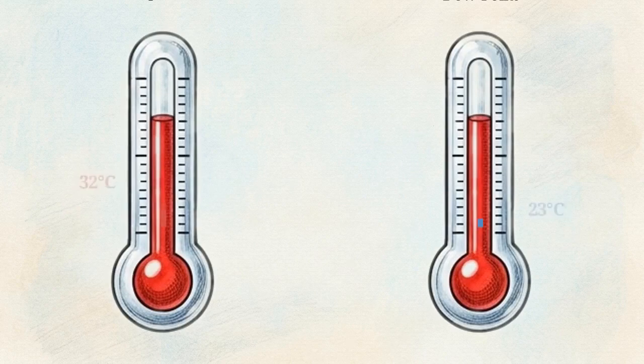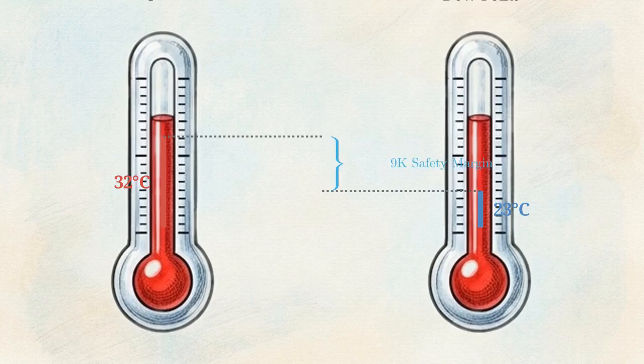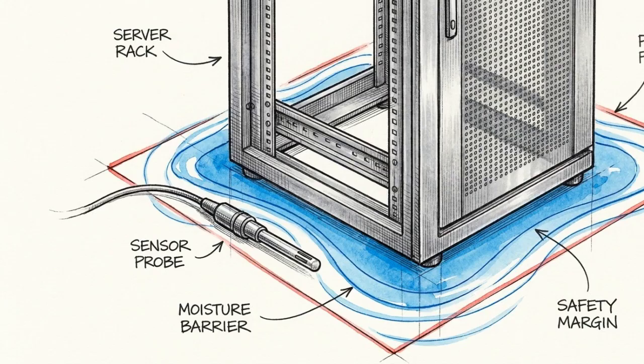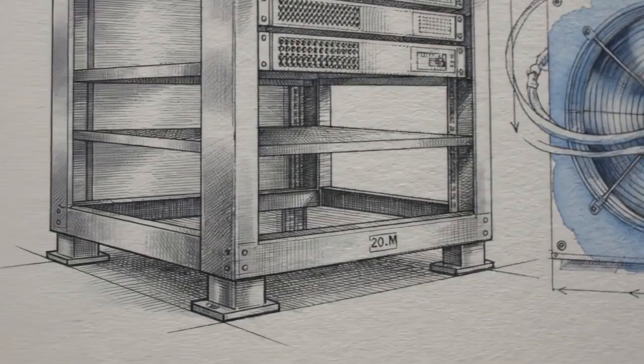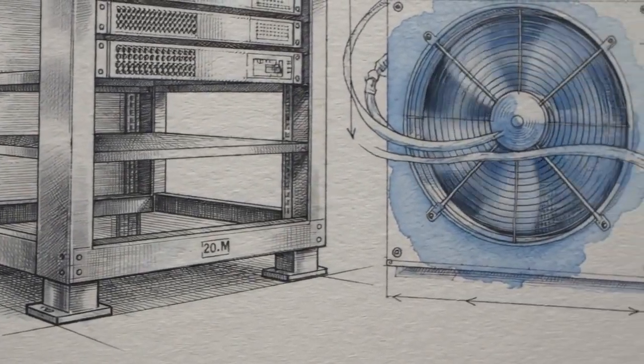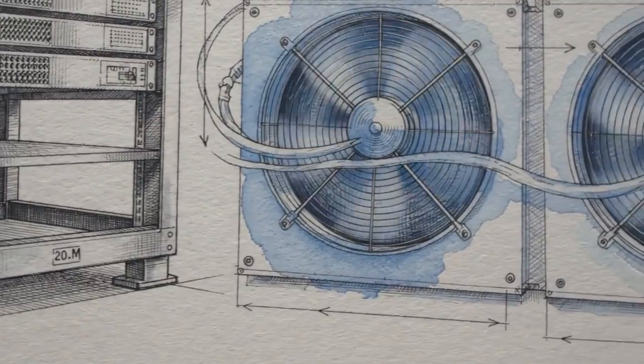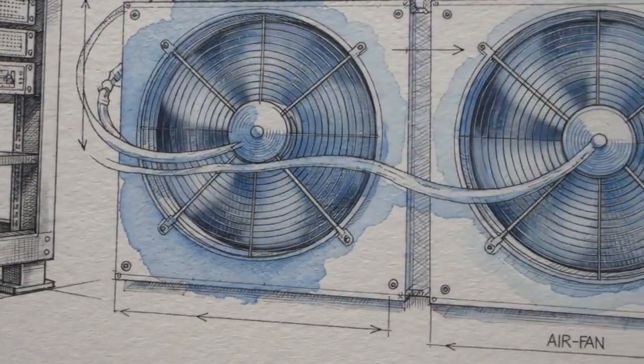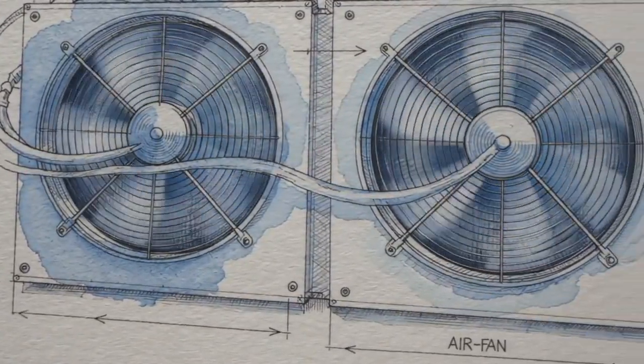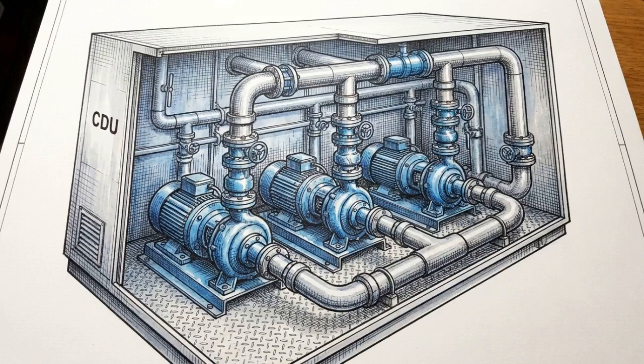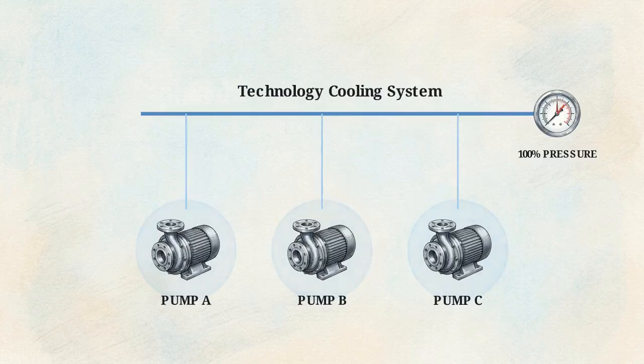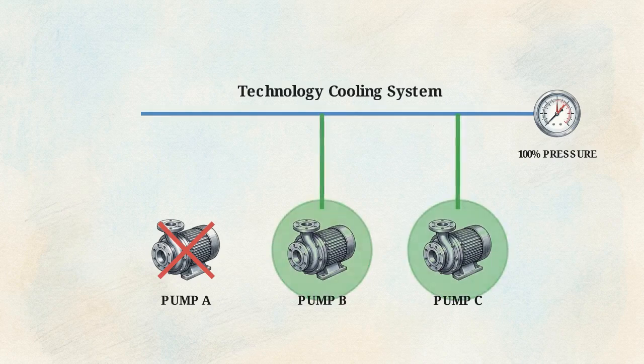It maintains a 32 degrees Celsius liquid supply temperature against a typical 23-degree room dew point, locking in a strict 9 Kelvin safety margin. That 9 Kelvin margin prevents localized frame sweating. It ensures no condensation drops onto the surrounding air-cooled legacy infrastructure running in the same hall. Inside the CDU modules, fluid distribution relies on true N+1 active-active variable speed pumps. If one pump fails, the others automatically ramp up to maintain exact loop pressure without interruption.